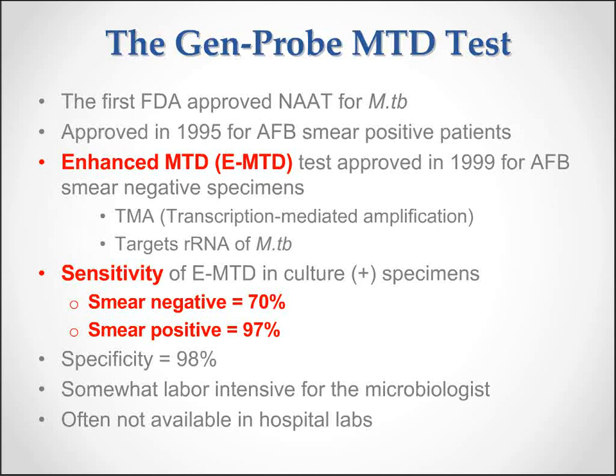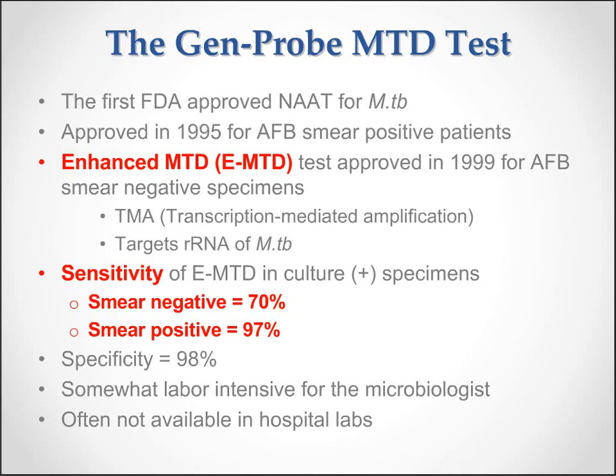Let's start with the Genprobe MTD test. This was the first FDA-approved NAT for Mycobacterium Tuberculosis, approved way back in 1995 — that's why I said 20 years — for AFB smear-positive patients. In 1999, an enhanced MTD test was approved by the FDA for use in AFB smear-negative specimens as well. The MTD test is a transcription-mediated amplification that targets the ribosomal RNA of MTB, of which there's about a thousand copies in every mycobacterium. The sensitivity in culture-positive specimens is quite good: approximately 70 percent for smear-negative and 97 percent for smear-positive specimens. The specificity is 98 percent, so almost 100 percent.